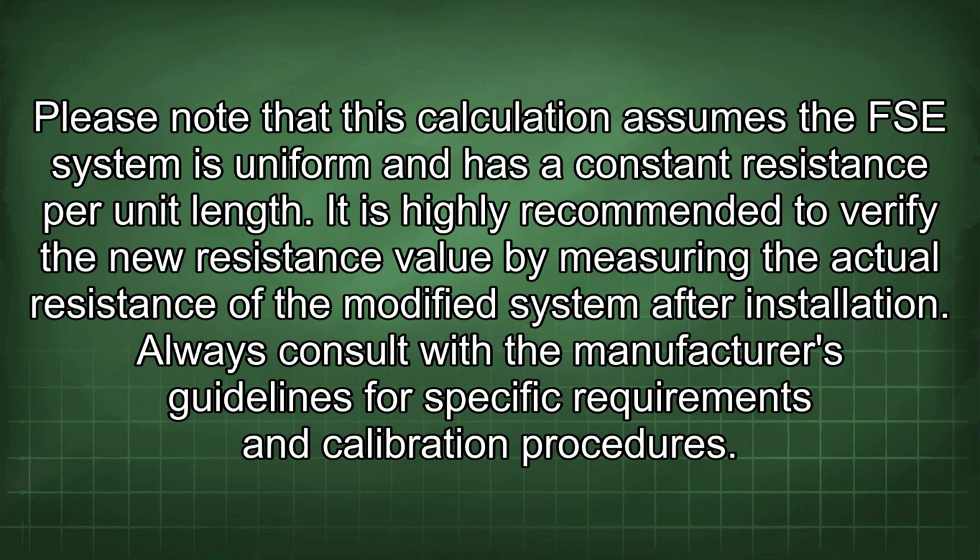Please note that this calculation assumes the FSE system is uniform and has a constant resistance per unit length. It is highly recommended to verify the new resistance value by measuring the actual resistance of the modified system after installation. Always consult with the manufacturer's guidelines for specific requirements and calibration procedures.